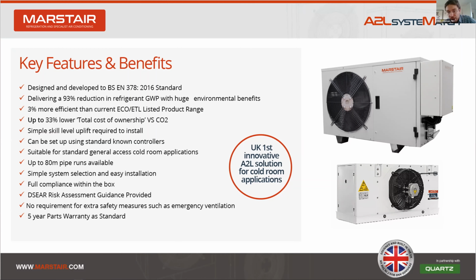We also have cost effectiveness. The A2L system costs will be much closer to current normal A1 systems, and there's a big difference compared to alternative green options such as CO2. So this, along with the improved energy efficiency, gives a very low total cost of ownership for the end user for such an environmentally green solution. We also give installers all they need for full compliance within the box. So basically, we're helping them. They don't need to fend for themselves.